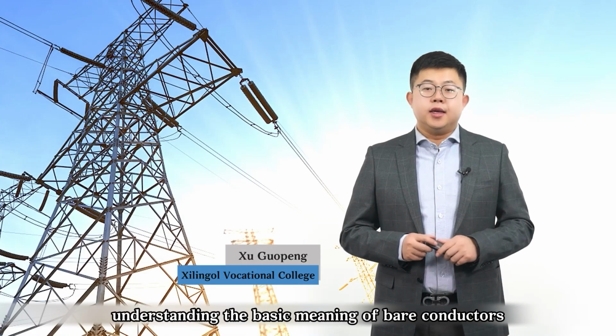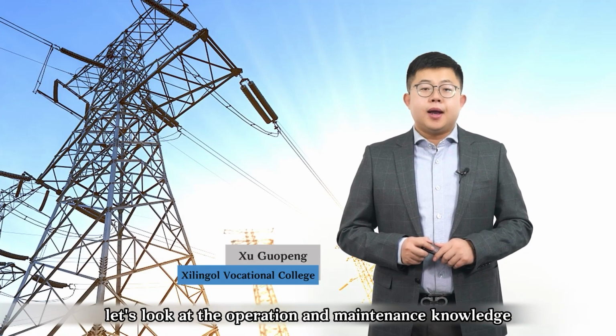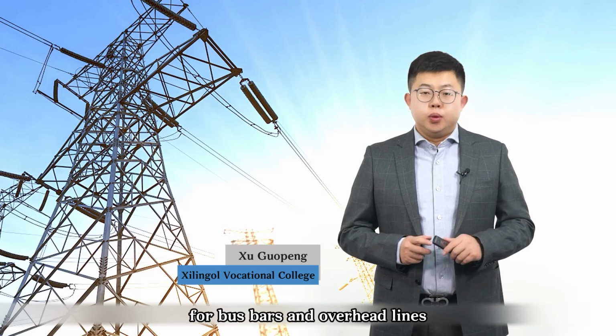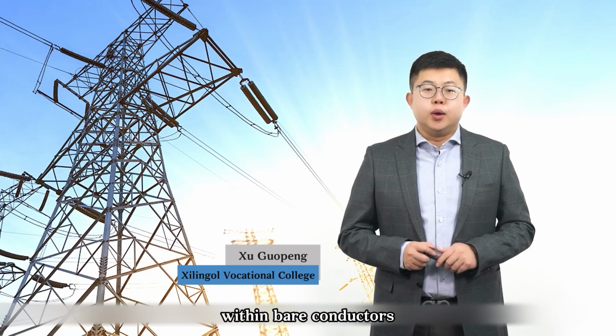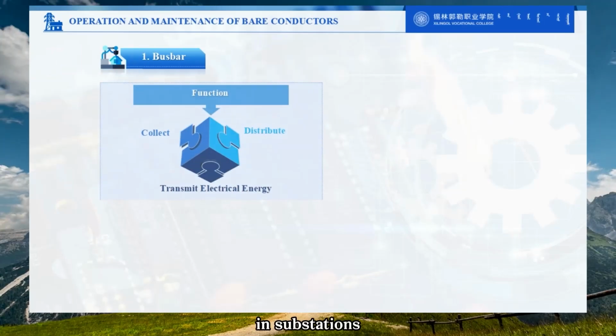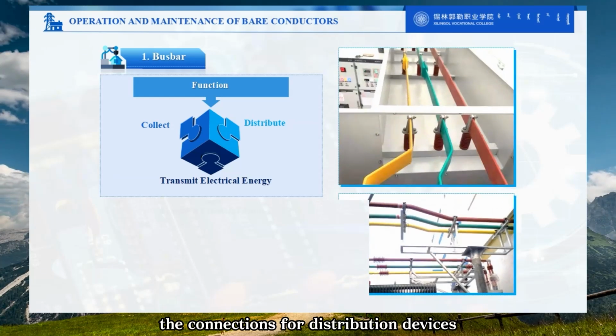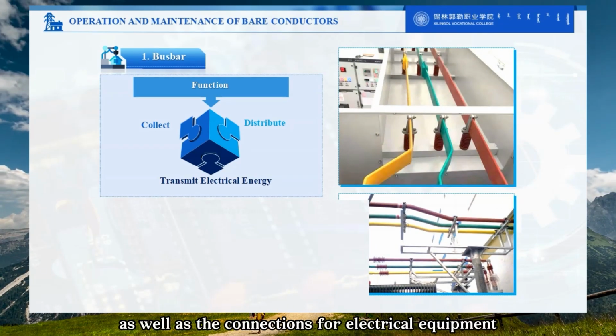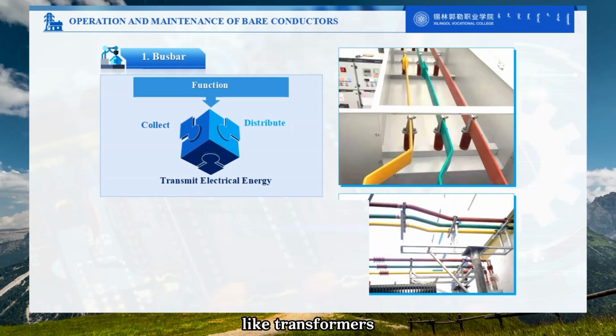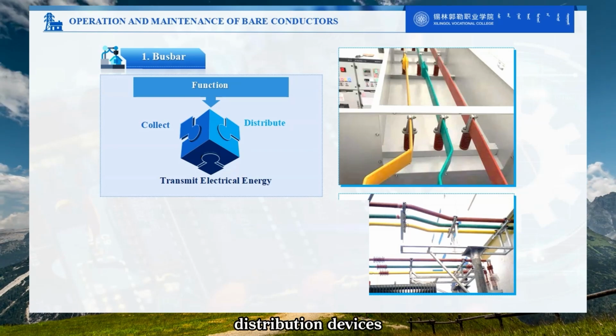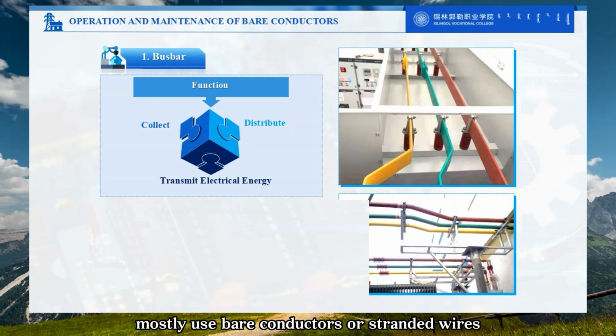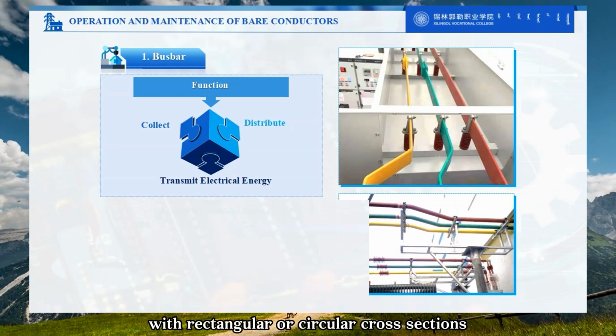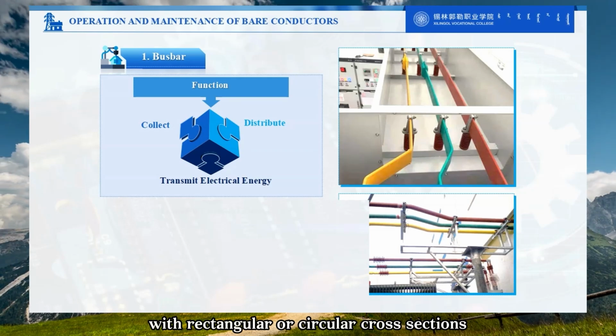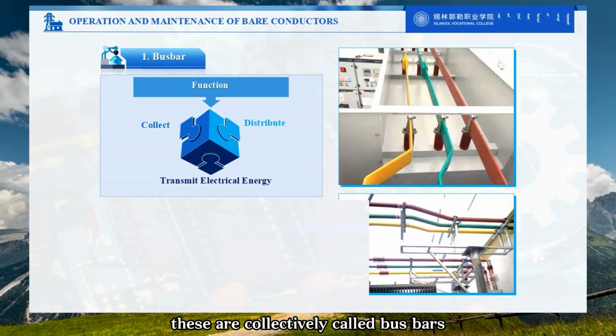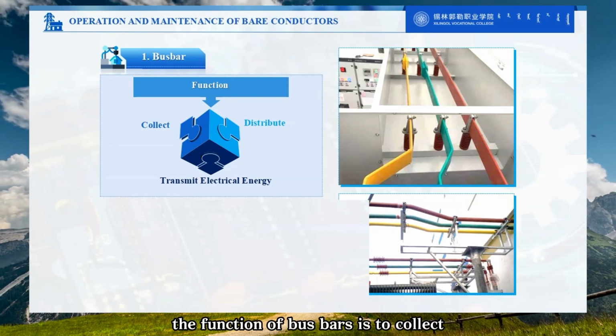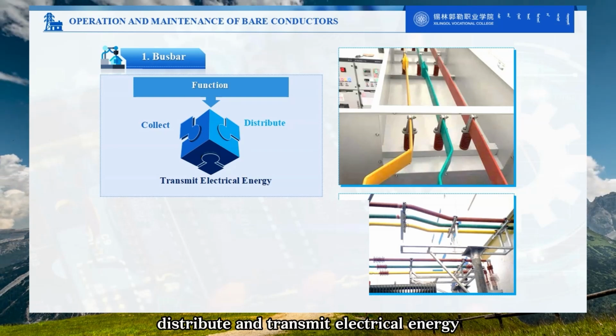After understanding the basic meaning of bare conductors, let's look at the operation and maintenance knowledge for busbars and overhead lines within bare conductors. In substations, the connections for distribution devices at various voltage levels, as well as the connections for electrical equipment like transformers and their corresponding distribution devices, mostly use bare conductors or stranded wires with rectangular or circular cross-sections. These are collectively called busbars. The function of busbars is to collect, distribute, and transmit electrical energy.